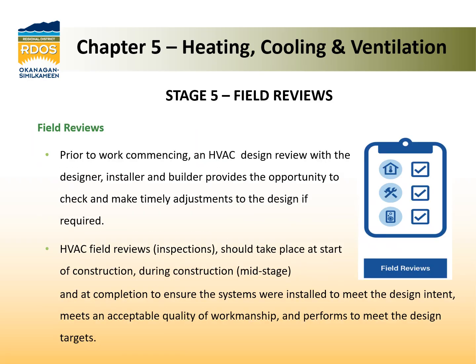Field reviews. Even the best of contractors may have a bad day, miss something, or misunderstand something. For these reasons, there must be a process of checking the installation. Ideally, if schedules and budget permit, the first meeting on site with the HVAC contractor, general contractor, and any others should occur when the structure is completed before commencement of installation. This would be the opportunity to verify the design against the actual structure, make design adjustments if required, and clarify any details that may not be clear in the design itself.